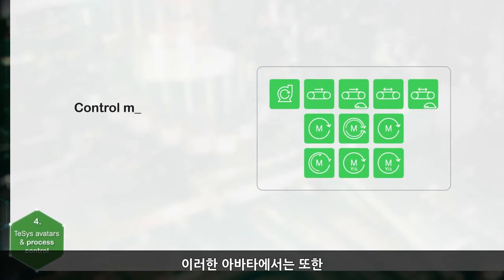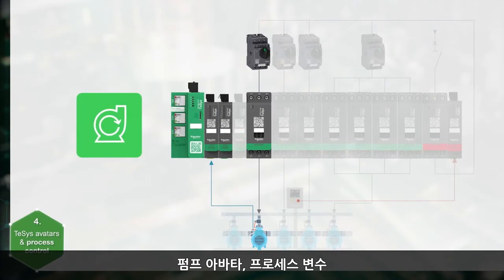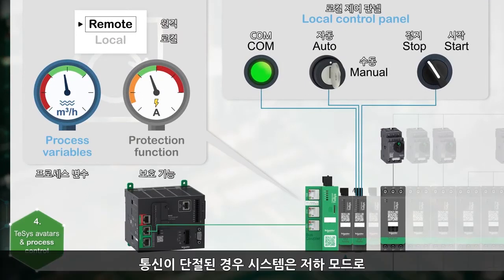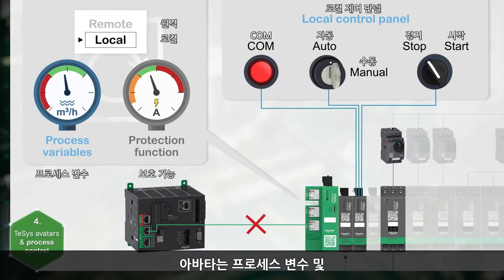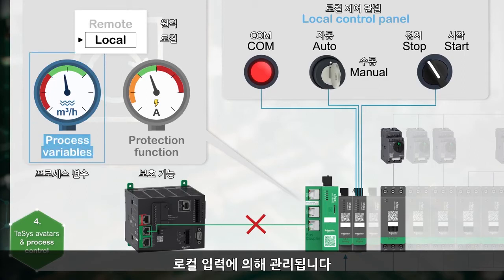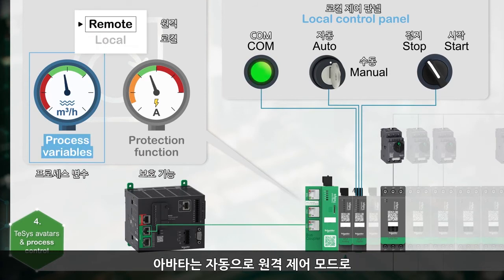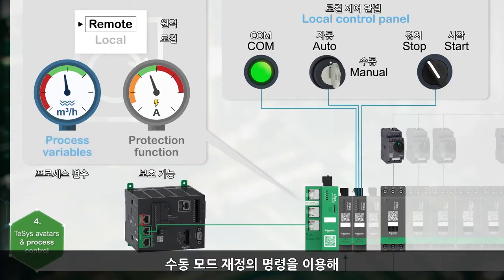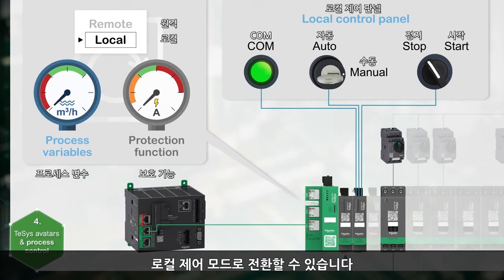These avatars also feature control mode selection in order to minimize downtime. Taking the pump avatar as an example: in case of communication loss, the system transitions to degraded mode and the avatar to local control mode. The avatar is then managed depending on process variables and local inputs. If set, the avatar can switch back to remote control mode automatically when degraded mode ends. It is also possible to switch the avatar from remote control to local control mode with the manual mode override command.